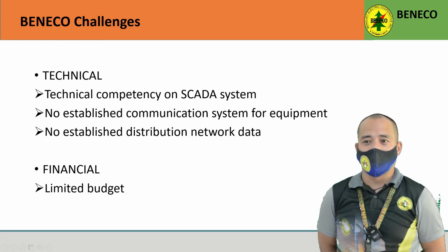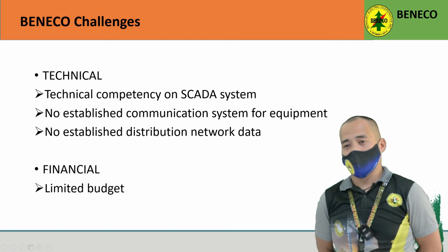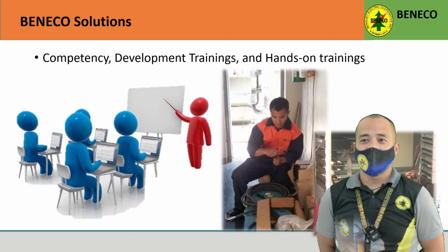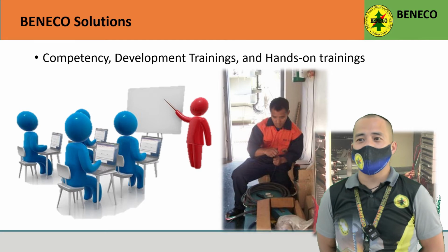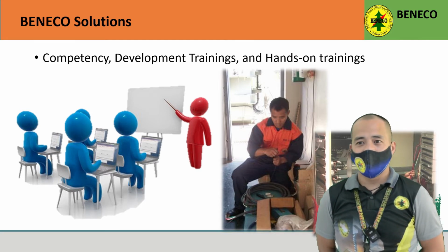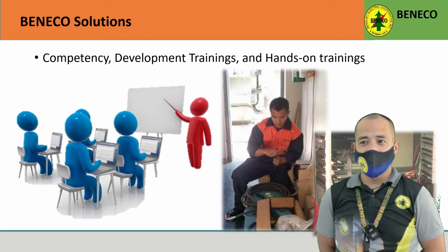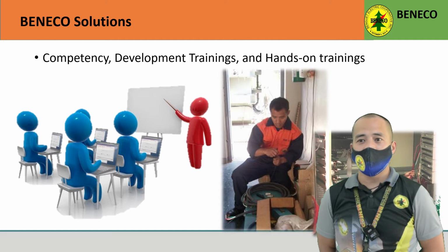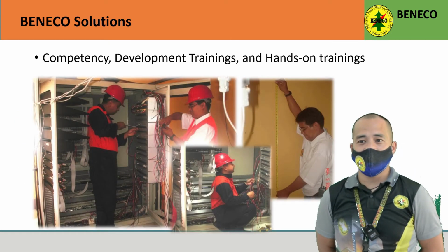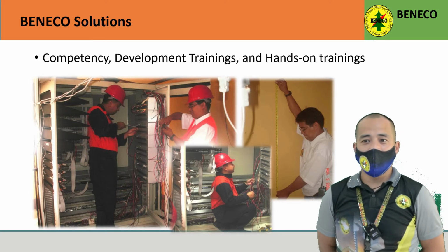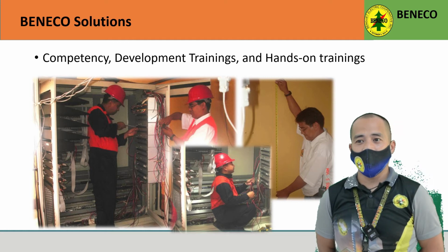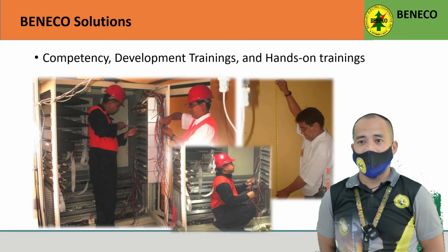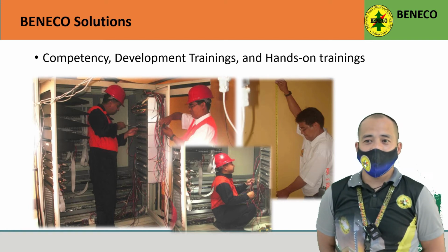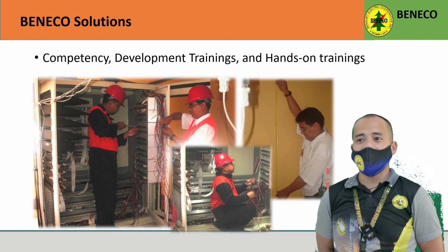Therefore, in order to overcome the technical and financial challenges, the following were done. Beneco provided for the competency, development, and hands-on training for its personnel. Hence, once the personnel were capable, they accomplished the project on their own. The personnel wired the equipment from the 69 kV air break switch down to the feeder circuit breakers, recloser. Lay out the wires in the trenches and likewise connected it to the SCADA panel. It was highly recommended that the personnel should be hands-on on the wiring of the protective devices, coupled with the SCADA panel, and also develop the SCADA software so that if a problem arises, they can easily analyze and troubleshoot it.